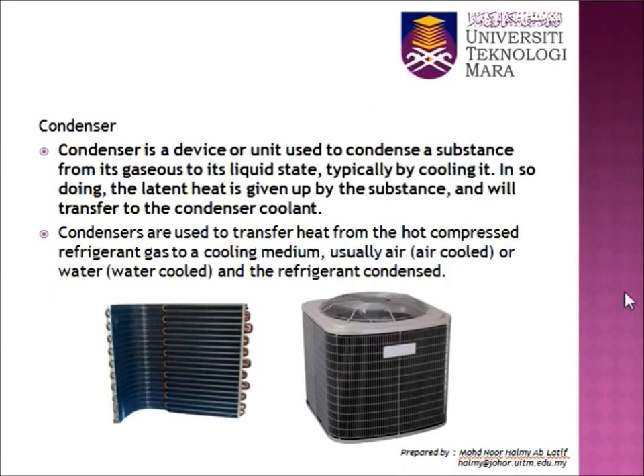Next component in aircon is condenser. So what is condenser? Condenser is a device or unit used to condense a substance from its gases to its liquid state, typically by cooling it. In so doing, the latent heat is given up by the substance and will transfer to the condenser coolant. So this condenser is used to transfer heat from the hot compressed refrigerant gas to a cooling medium, usually air cool or water cool, and the refrigerant condenses.